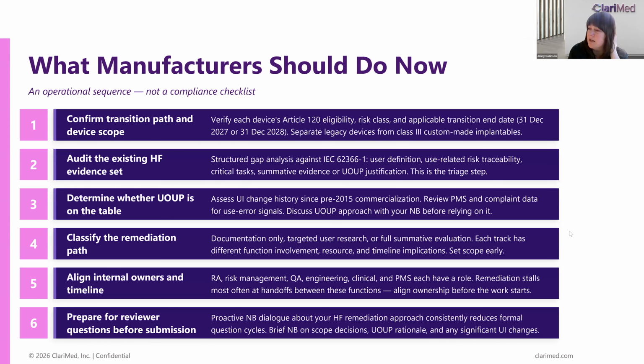I think what I would add to that is that they perform reviews in a slightly different way to people who are used to dealing with the FDA. They're very much applying their rigor to whether you've adhered to a standard. My experience with certain notified bodies is they go through a checklist. Does someone have a use specification? Do they have this section complete?